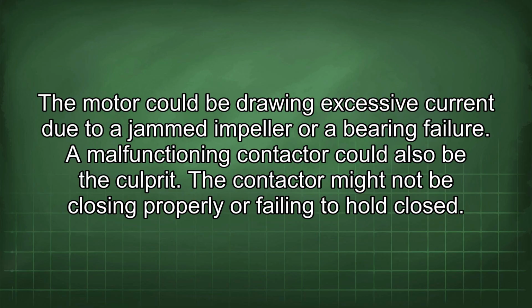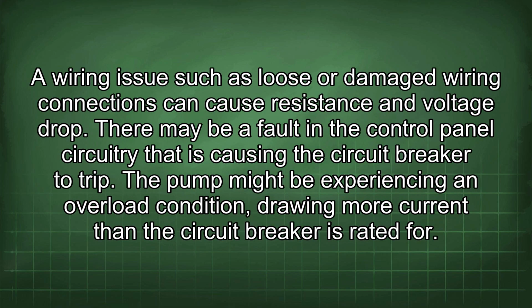A malfunctioning contactor could also be the culprit. The contactor might not be closing properly or failing to hold closed. A wiring issue such as loose or damaged wiring connections can cause resistance and voltage drop. There may be a fault in the control panel circuitry that is causing the circuit breaker to trip. The pump might be experiencing an overload condition, drawing more current than the circuit breaker is rated for.